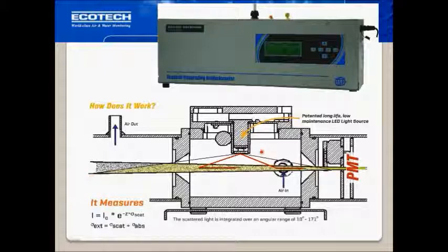Light exiting the light source at an angle like that hits a particle here, the light gets scattered towards the detector, and so you have a scattering angle which is basically a backward scattering from here to here. Light going into the forward direction hits a particle here, gets scattered in that area, measured here, and you have a smaller angle scattering, a forward angle scattering, and all gets measured with the photomultiplier.